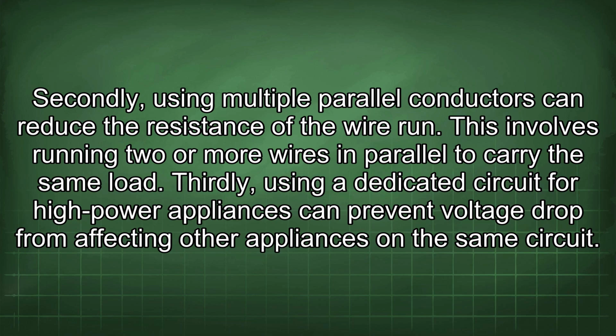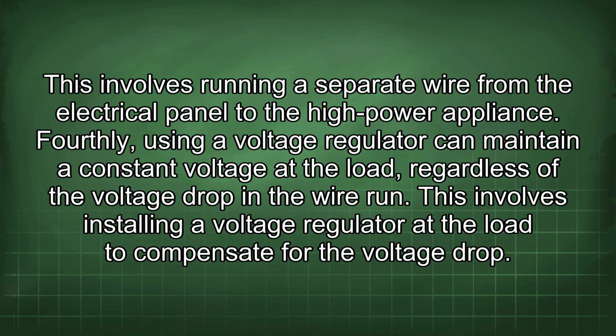Thirdly, using a dedicated circuit for high-power appliances can prevent voltage drop from affecting other appliances on the same circuit. This involves running a separate wire from the electrical panel to the high-power appliance. Fourthly, using a voltage regulator can maintain a constant voltage at the load, regardless of the voltage drop in the wire run. This involves installing a voltage regulator at the load to compensate for the voltage drop.